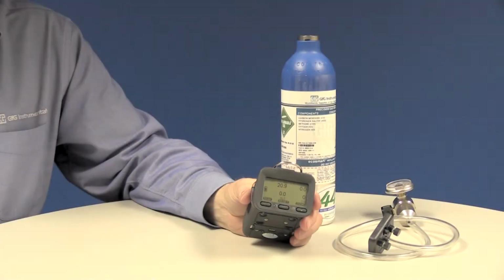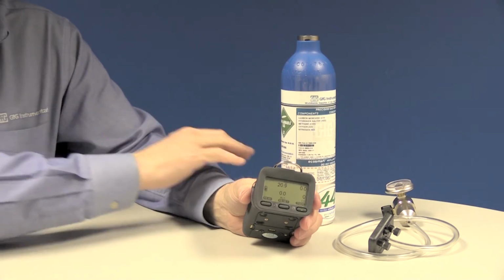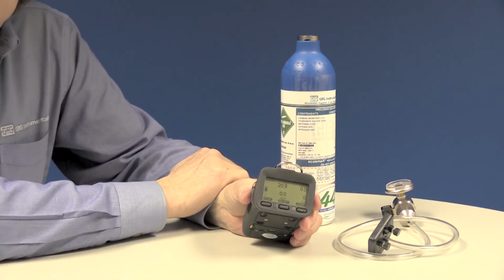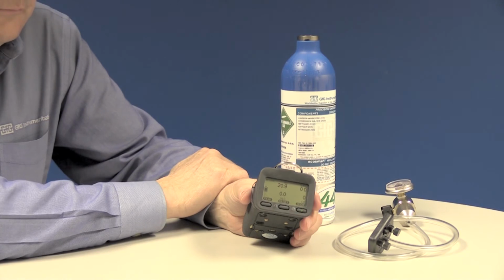Make sure the instrument is located in fresh air. In fresh air, the instrument should show readings of 20.9% O2, 0% LEL combustible gas, 0 parts per million CO, and 0 parts per million H2S. Even when the readings show the correct fresh air values, you should still perform a fresh air autocal adjustment before performing a gas autocal adjustment.